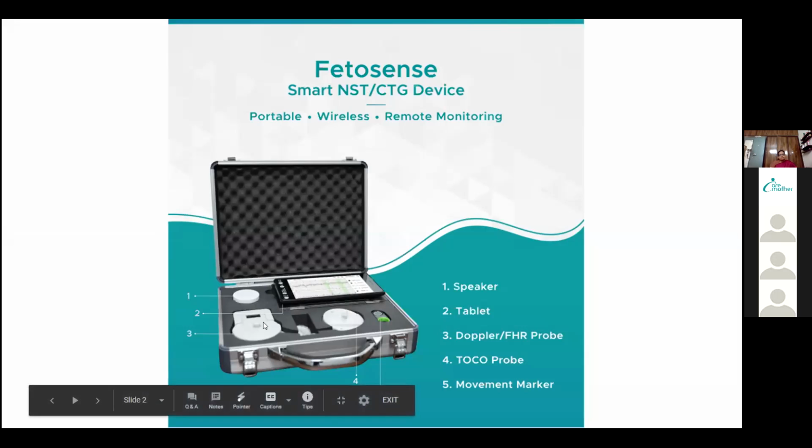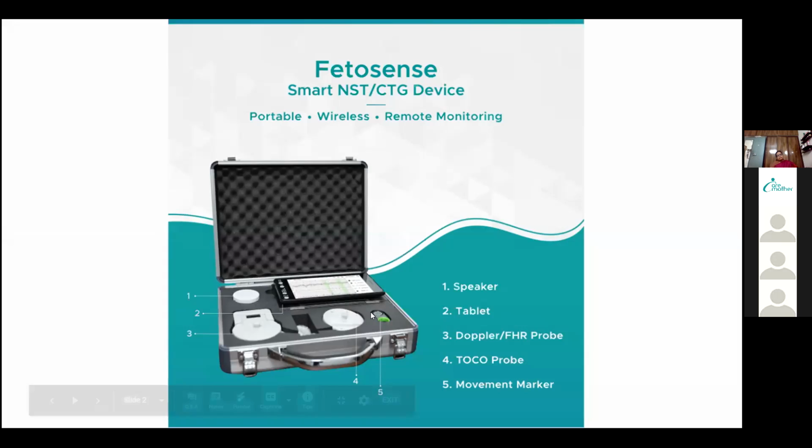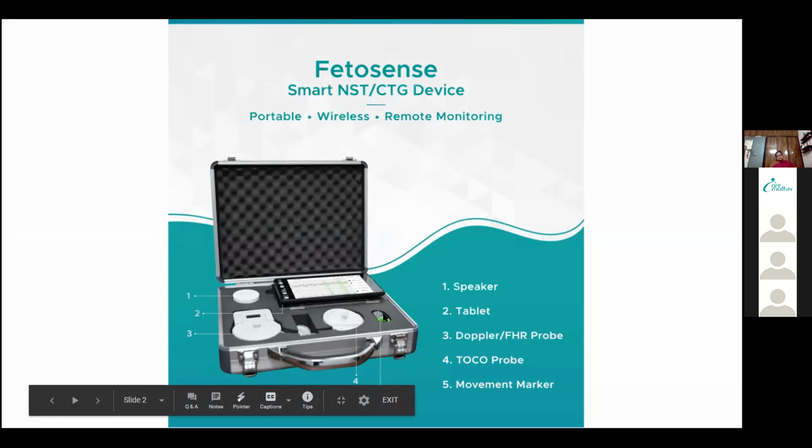There is the NST or the FHR probe. Then we have the cardiotocography probe. Then we have a manual movement marker, which we give to the mother to trace the baby's movements. And then there is a speaker to amplify the baby's heartbeat sound.